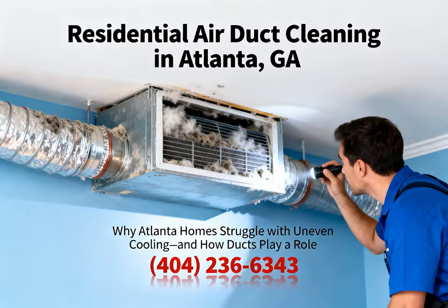Okay. But the standard 1-inch fiberglass filters most people buy at the grocery store are practically useless against the microscopic particulates that cause sludge. Really? The ones you just slide in? Yeah, those cheap filters are essentially designed to catch boulders. Things like pet hair, lint, large dust bunnies. They're just there to stop them from physically striking the blower motor. Oh, I always thought they were cleaning the air. A lot of people do. But they do virtually nothing to stop the fine 1-micron particulates from passing right through and entering your airstream.